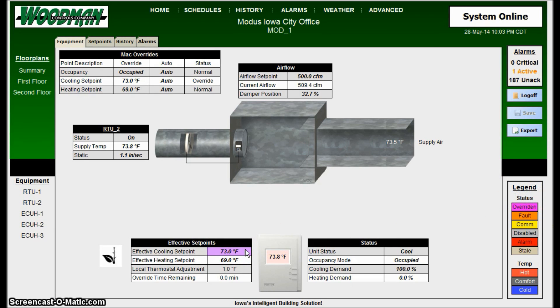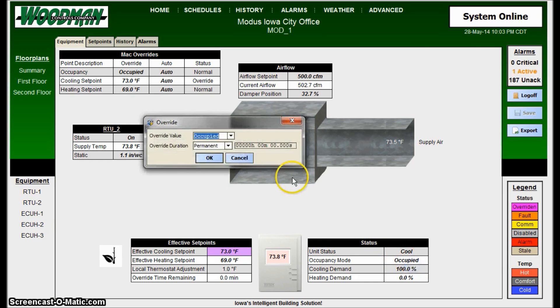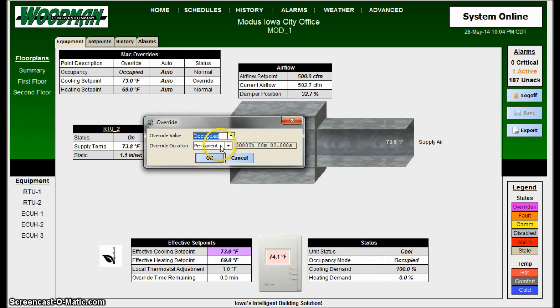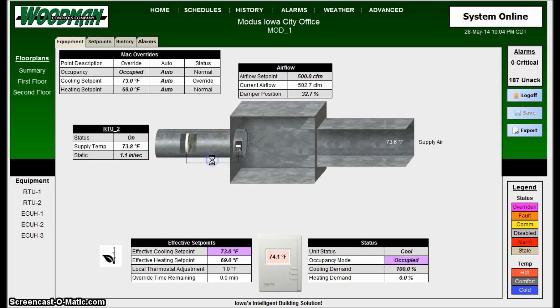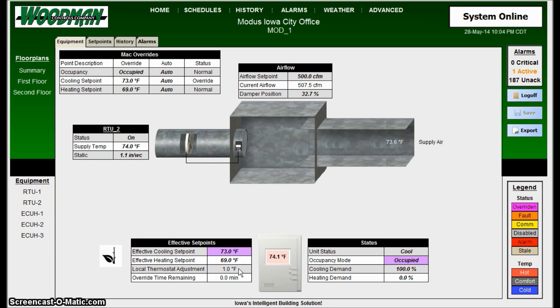That point is in override and the equipment is going to operate to that set point right now. Same for occupancy mode — if you want to override this room to be unoccupied, you just select whatever mode you want and pick a period of time. This is how you do overrides on a system. Same for airflow. Anything that is bold or italicized is an overrideable, commandable point. If it's just typical text that's not bold, that is a status point, not overrideable.